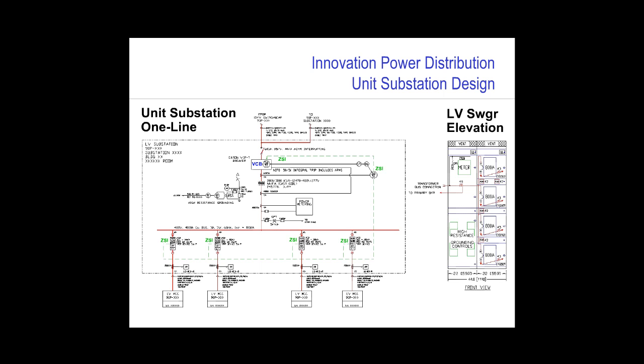The primary vacuum circuit breaker is actually controlled via 2 relays, one an integral tripping relay protecting the secondary bus with the appropriate short time settings to coordinate with the feeder breakers on the secondary, and two via a separate 50/51 protective relay on the primary connected to primary CTs set to protect the transformer. The integral trip unit in the primary vacuum breaker would also include the ARMS function, allowing me multiple settings groups so that I could set up a maintenance mode in the event that I needed to work on or rack in and out the secondary power circuit breakers in this substation.